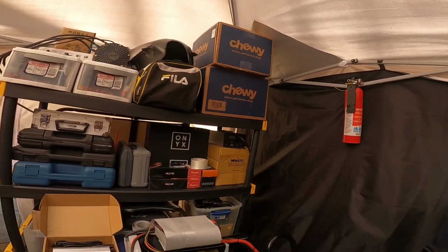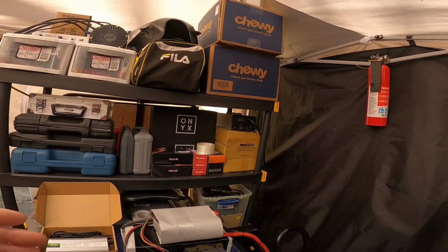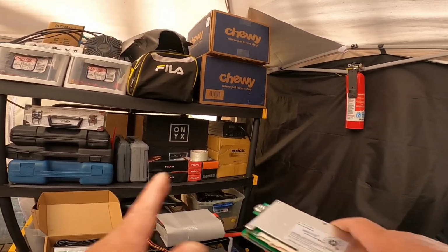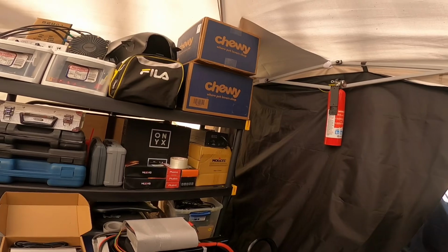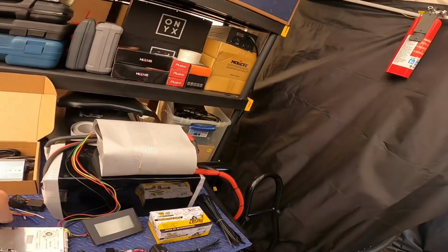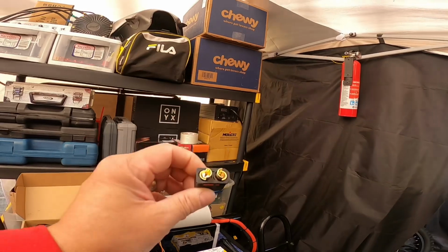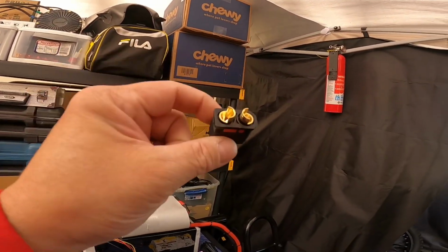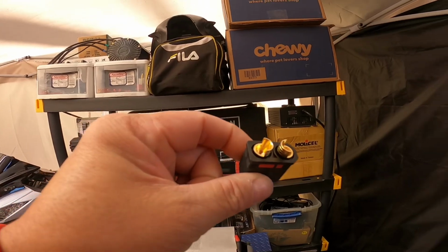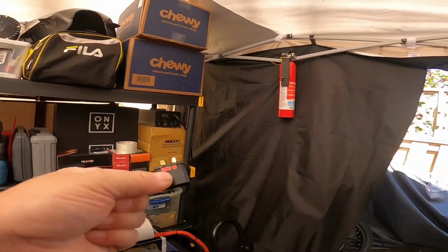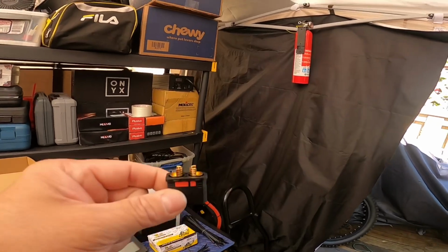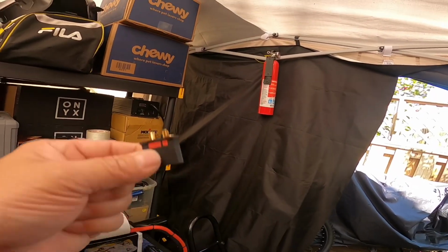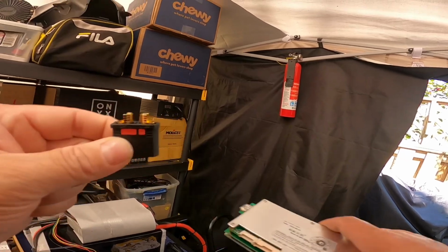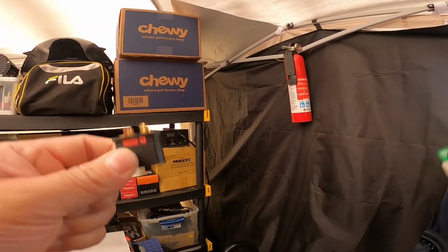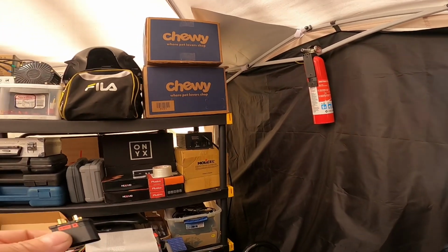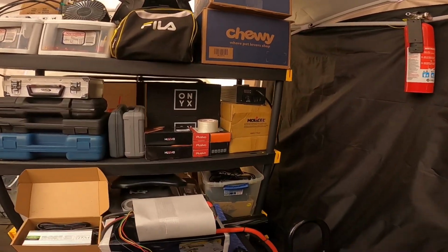And again, bottlenecks cause voltage sag. There's no doubt about that. It's a proven fact. Okay, even a connector that's not designed to carry the same amount of amps as the battery can produce, or the wires, is going to be a bottleneck. All right, you're going to get voltage sag from any parts of your power system that can't carry the power at a low resistance.